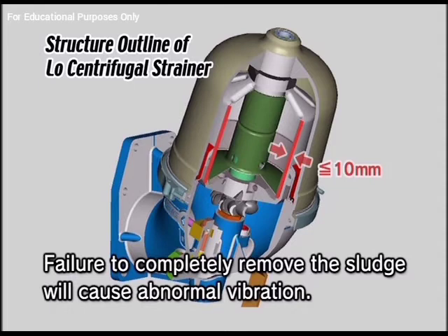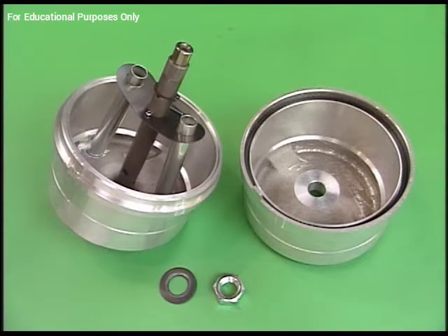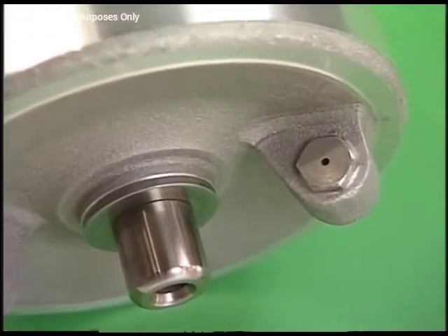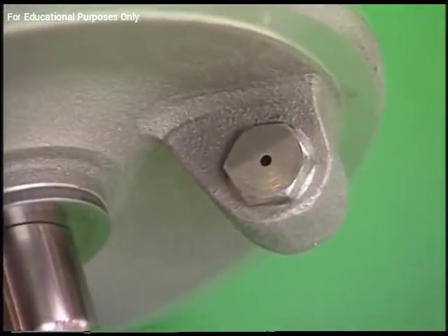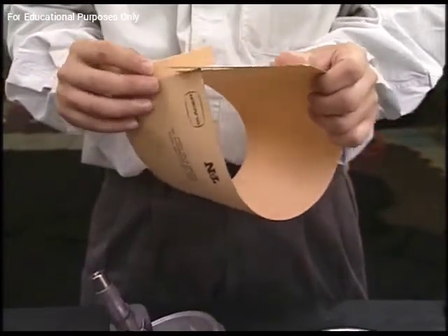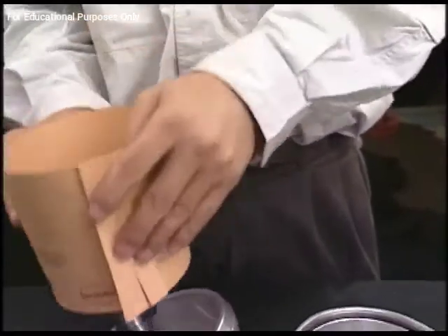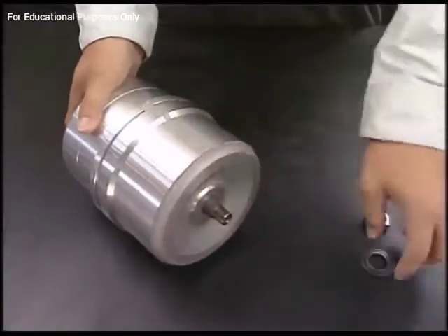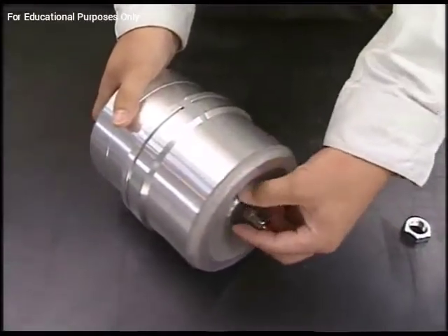Remove the sludge on the inside wall of the rotor. If the thickness of sludge deposition is over 10 millimeters, the cleaning effect will not be produced. Clean the rotor body and rotor cover, and check for clogging of the nozzle. After renewing the O-ring, reassemble the centrifugal bypass strainer in the reverse procedure. If a paper insert is put in, it will be easy to remove the sludge next time.